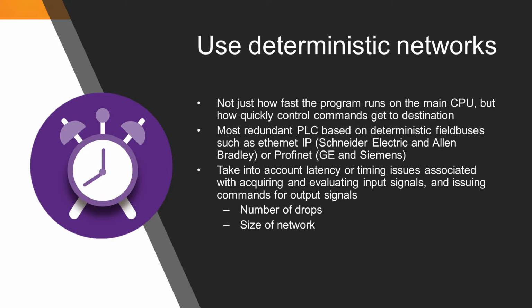For example, Allen Bradley and Schneider Electric use what's called Ethernet IP, and GE and Siemens use Profinet. Just be aware that if you look at a solution and you're told the distributed I/O network is using something non-deterministic, that should throw up a caution flag for you to ask more questions.